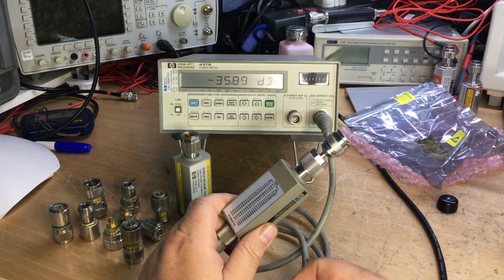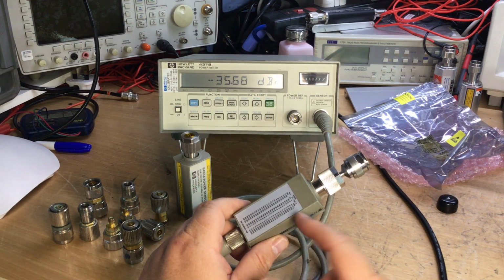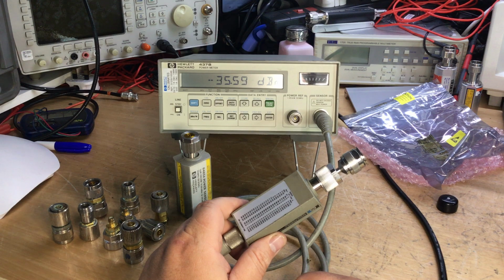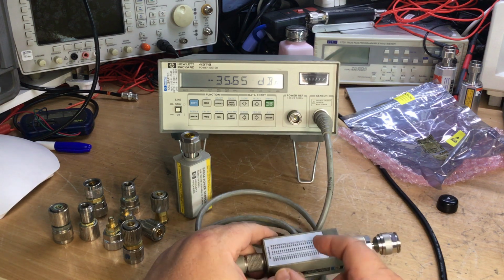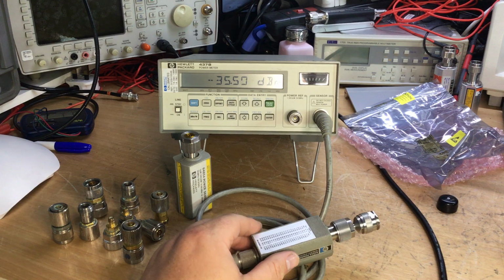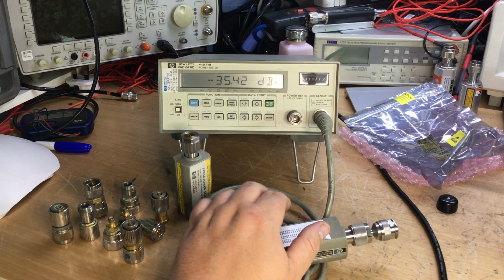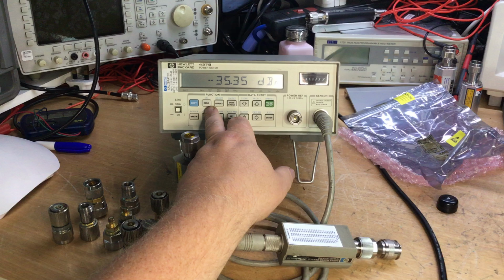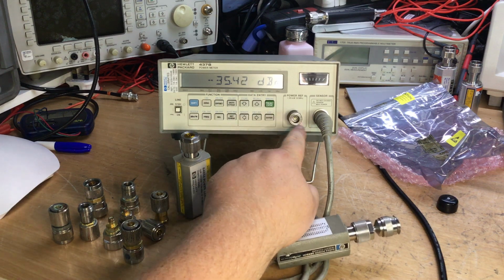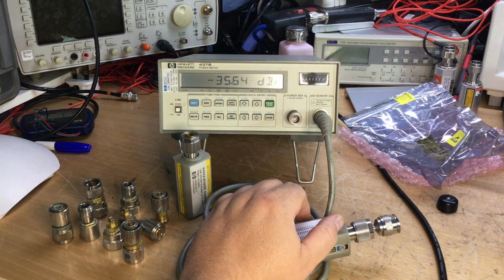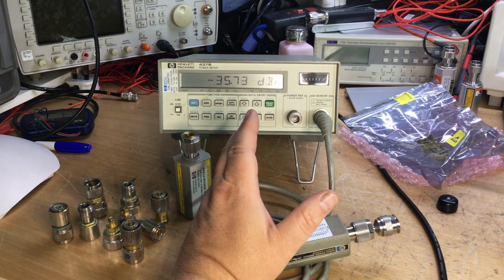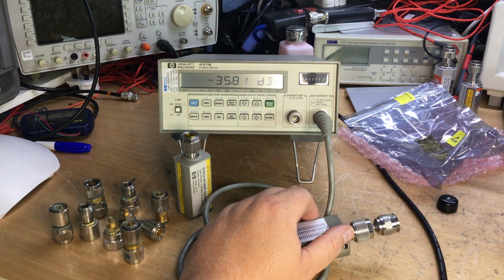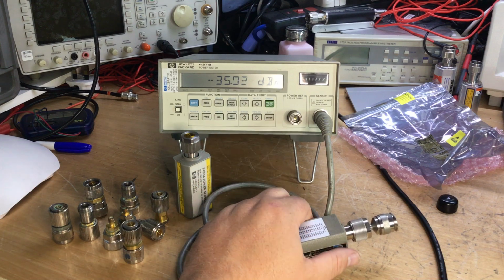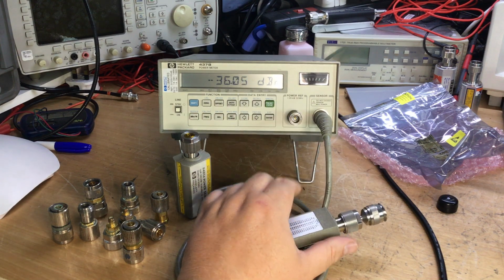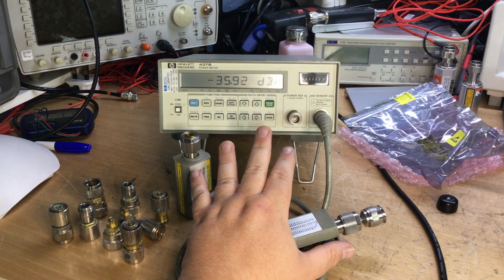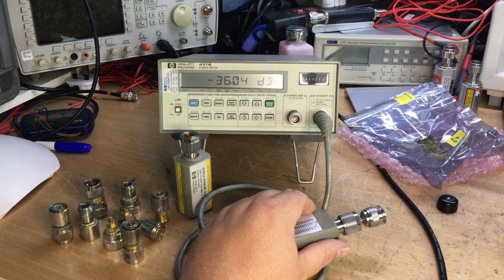Now the meter recognises the different types because it reads the sensor when it's connected in, and we can use the meter to calibrate the sensor by using the cal feature which is on the meter, which is these cal buttons here, and we have the type N output here which gives 0 dBm, or equivalent to 1 milliwatt, at around 50 megahertz as the cal signal to these sensors. So that's initially how we'll know that these sensors work.